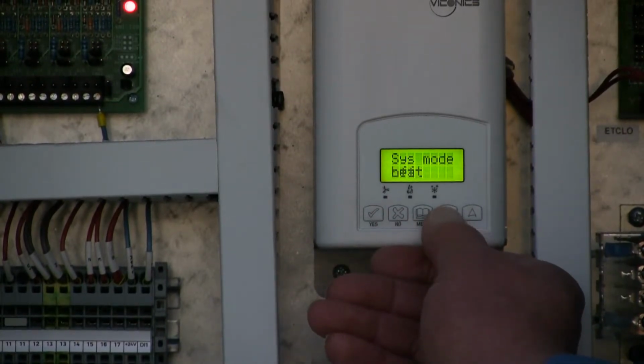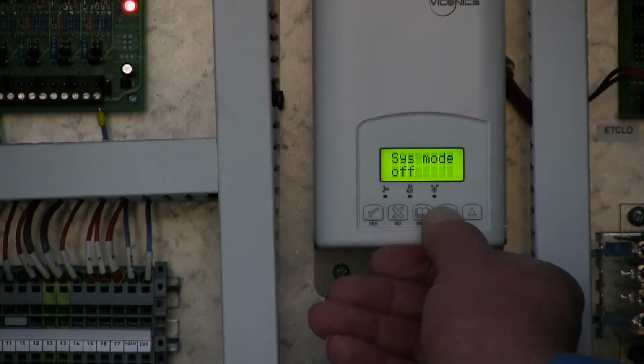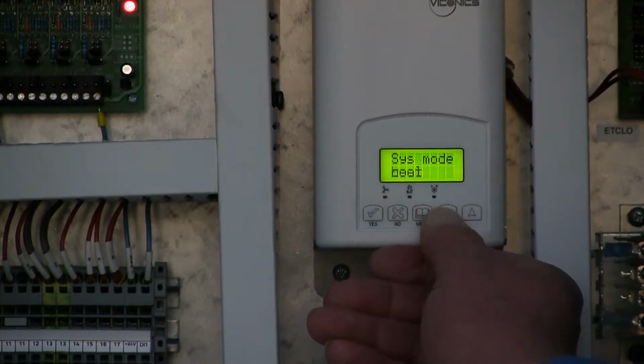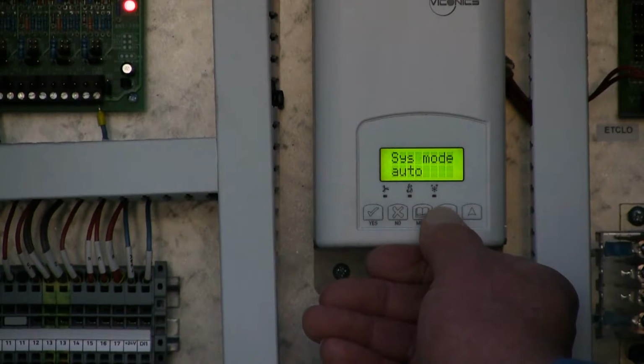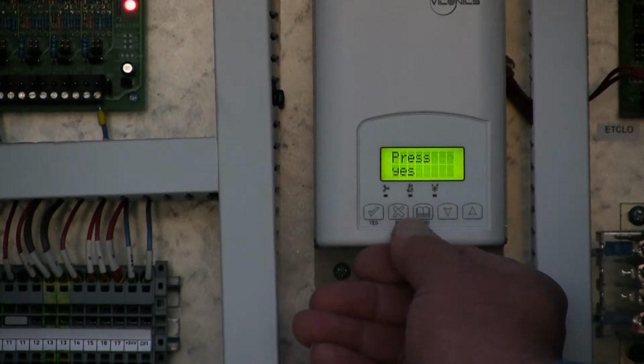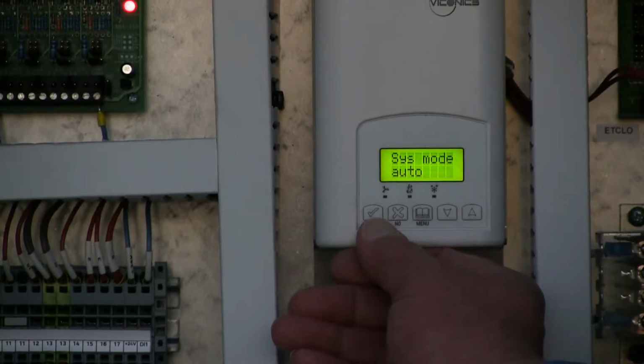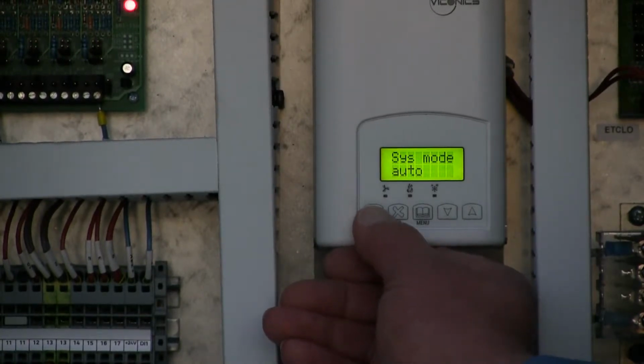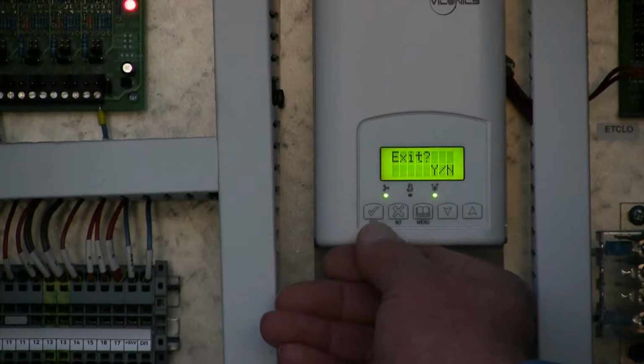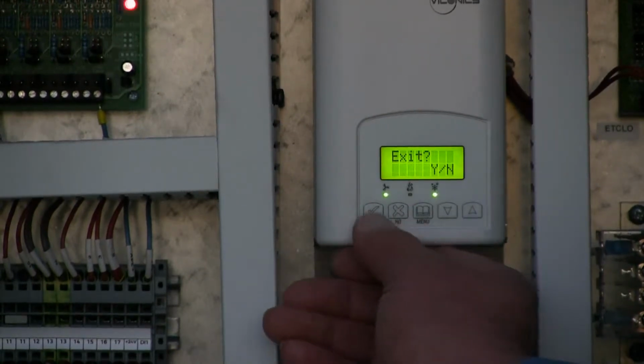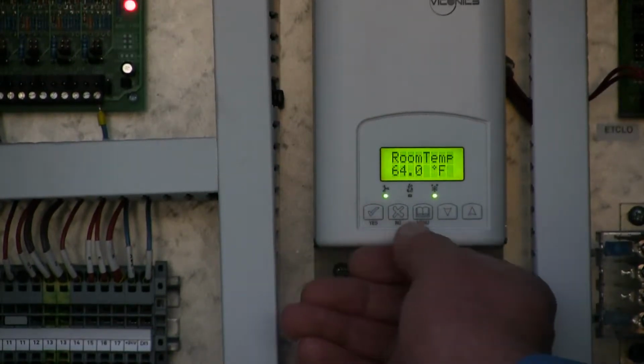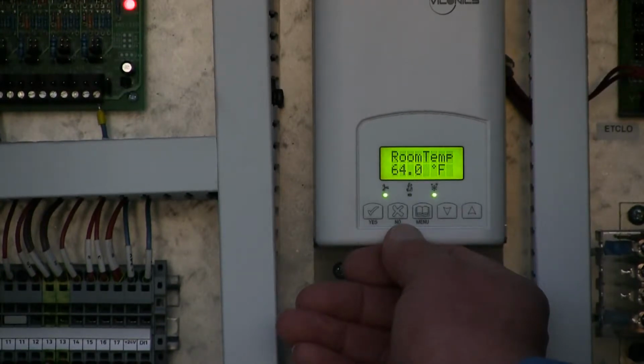So yes, we want to change the mode, so we're going to say yes. And we're going to change the system mode to heat. You can see I can go through all of them and it just rotates around. Off, heat, cool, or automatic. If you put it in automatic, then you can set the heat set point and the cool set point and be able to run the machine in full automatic. So we're going to select auto, and we're going to say simply yes. Exit, yes or no. We're going to simply say yes. The room temperature is 64 degrees.